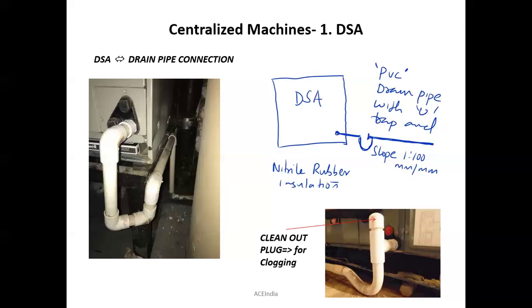So what is the purpose of a U-trap? Guys, as the water starts to flow across these pipelines, and as we studied, inside these machines you will be having closed type centrifugal fans. So there is a high chance of water being reverted back into the drain pan itself due to the suction of the fan. And thereby this water would be sprayed again along with the supply air itself, which causes some humidity imbalance inside the rooms. So that's why we must choose a U-trap.